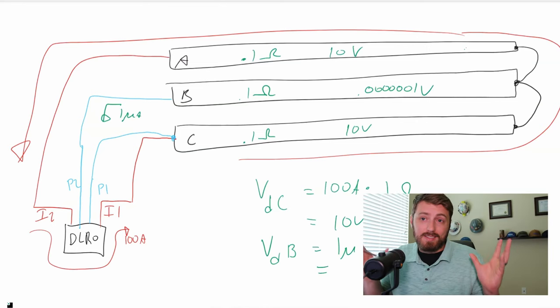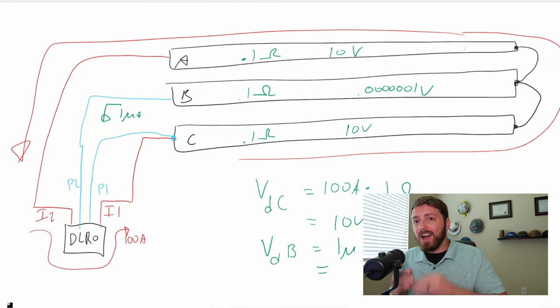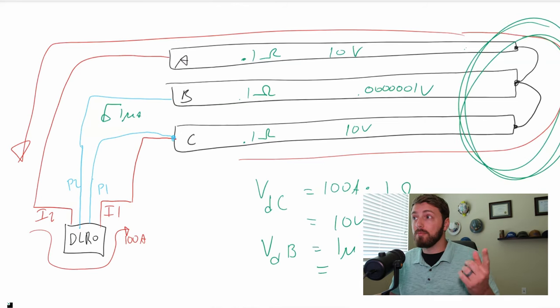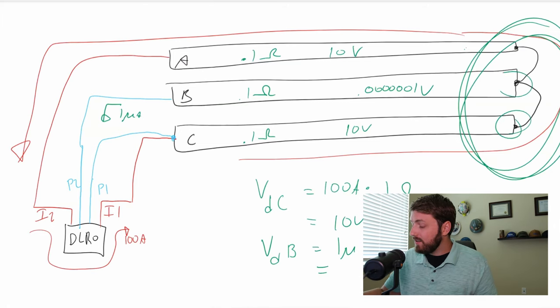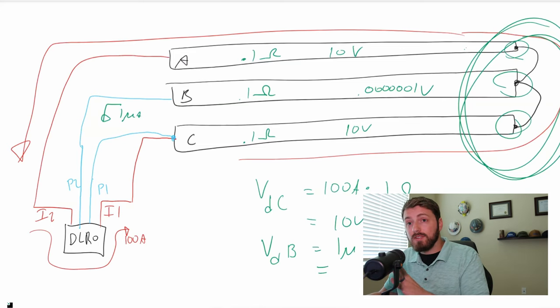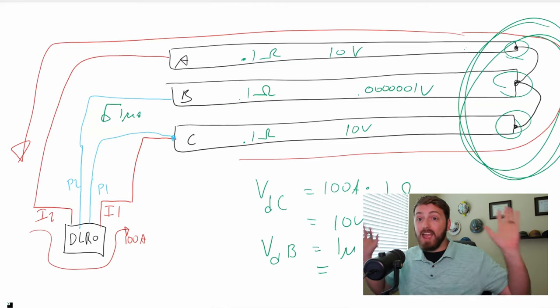What this means is on a three-phase installation of bus duct, whether it's ABC, or ABC and neutral, or ABC, neutral and ground, or however it's configured, as long as I've got three or more phases in the bus duct that are relatively the same and can carry the same relative amount of current, I can use the other phases as part of my test lead. So the only caveat, the only thing I really need to watch out for here is that on my far end, number one, whatever I'm using to connect the phases together is rated for the test current. If I'm using a 100 amp test set, I really need to have large jumpers on the other end. And the resistances here need to be fairly low, because if one of those is off, it's going to throw off your other readings. But assuming we can control for that, which is not that difficult in the field, I can use the other two phases as my test leads, and it comes out perfectly accurate.